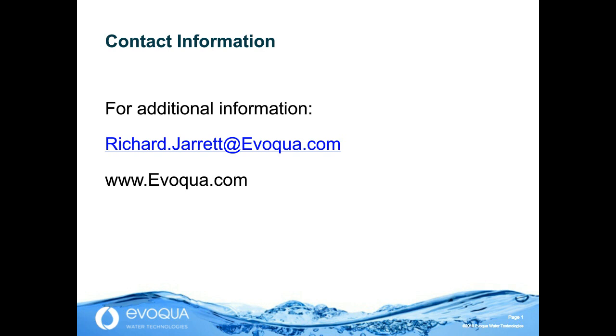I think manufacturers putting an endotoxin log reduction rating is important. So that way there's been some proven capability for the UF to do endotoxin reduction, so that then you feel comfortable about the final water quality, between a reduction, say in reverse osmosis, which isn't 100% preceding UF, but in most cases, between the two membranes, obviously the system, you don't want it to project to just meet the critical quality attribute of endotoxin. You would want to be comfortably below.